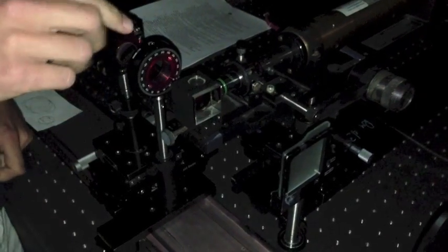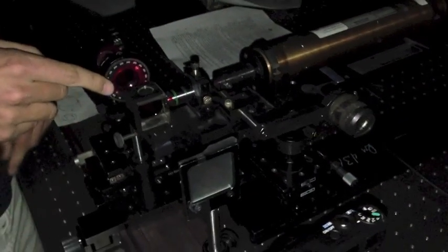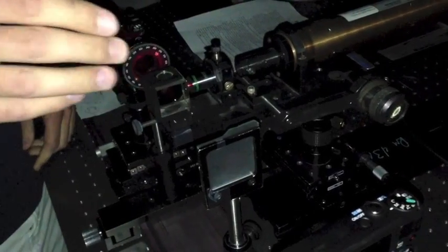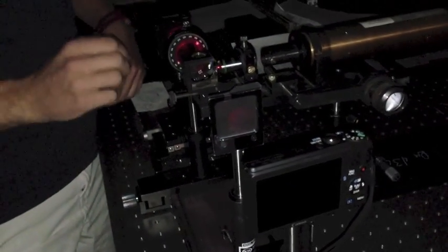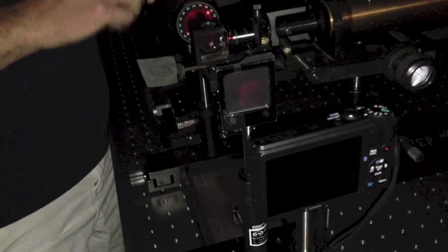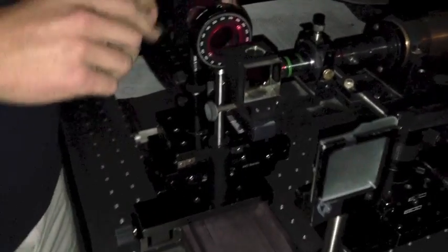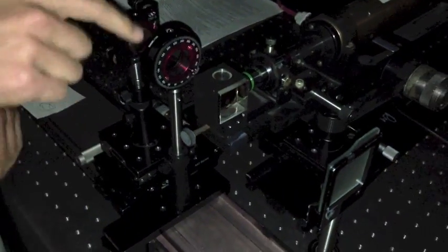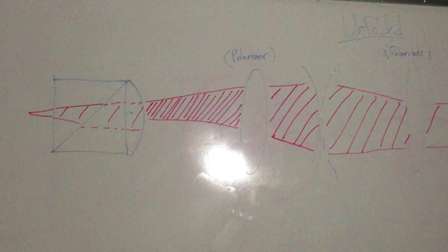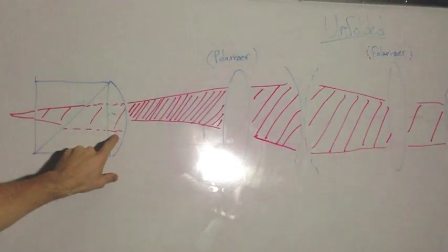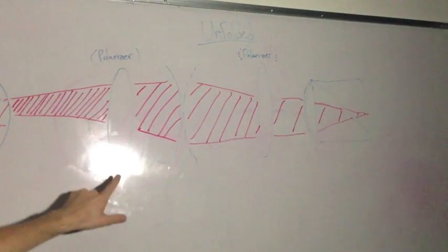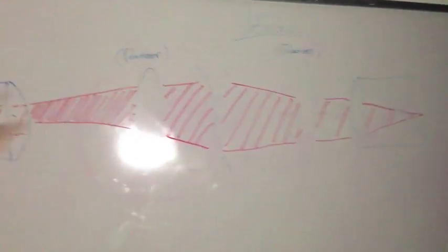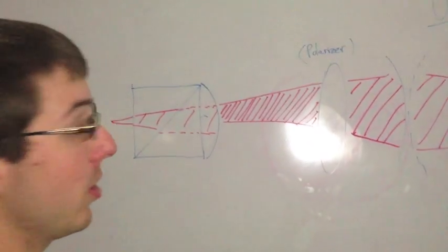Reference image is formed by a reflection off of a glass air interface. We know that only a small amount of light will return back to our screen, about 4%, so we need to cut down on the light returned from the mirror in order to improve contrast and visibility of fringes. We do that by using a linear polarizer. When we're testing the mirror, the light that gets reflected back from the shack cube is much dimmer than the light that gets reflected from the mirror. So we use a polarizer to make the intensities match and the fringe visibility goes up.